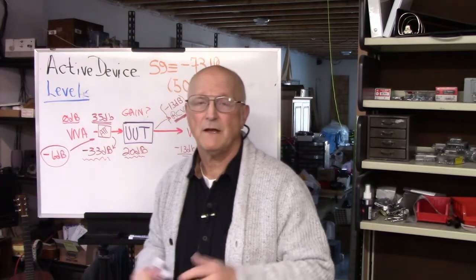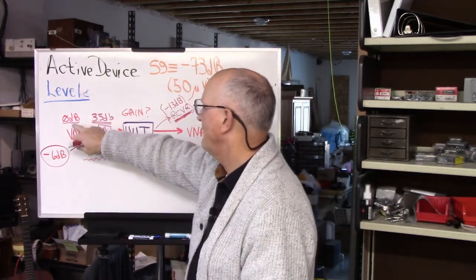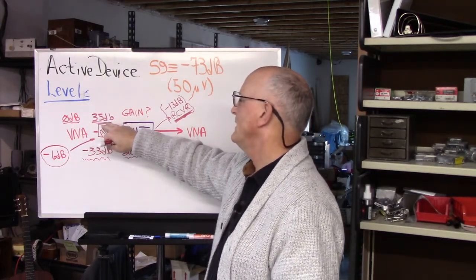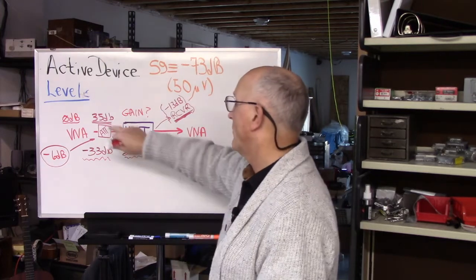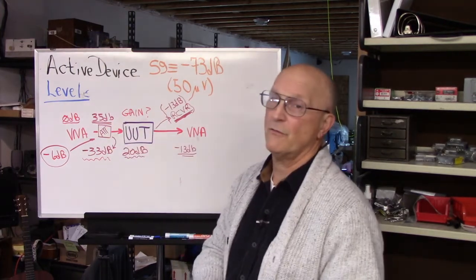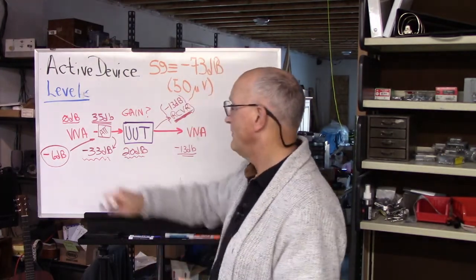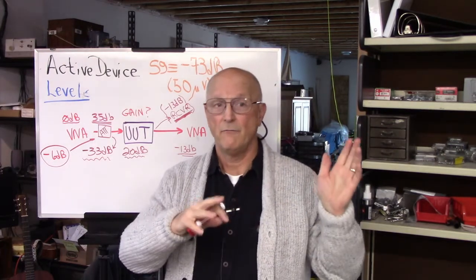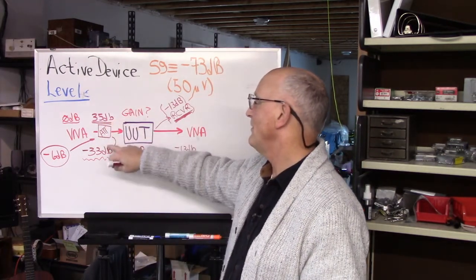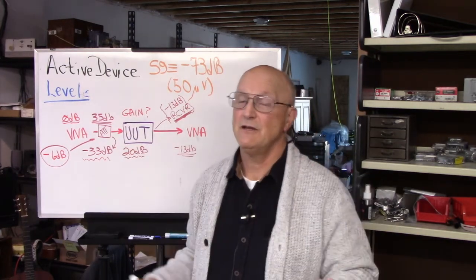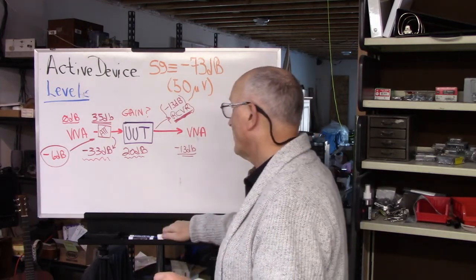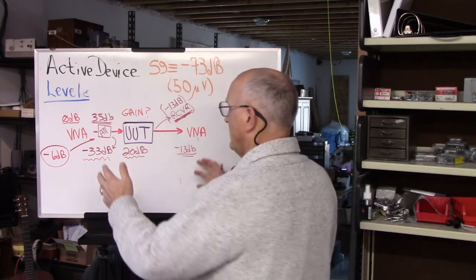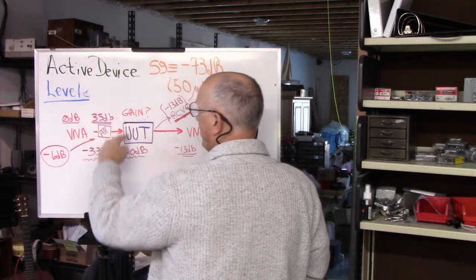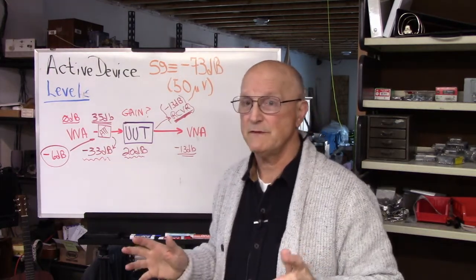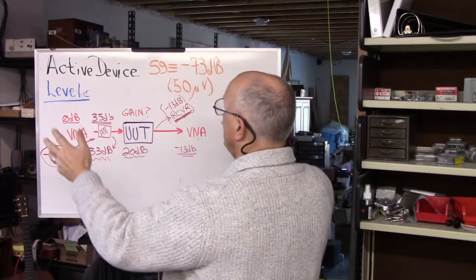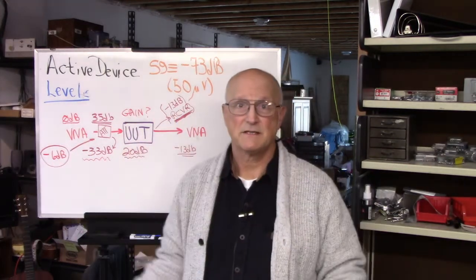Now with my HP VNA, the lowest I can adjust my power level is minus 10 dB, so I could use a 25 dB attenuator here, or a 30, let's say a 30 dB attenuator here with that one. With the Tektronix VNA, the newer one, I can actually adjust the output of my VNA all the way down with a source level of minus 35 dB. So I don't even need to use an attenuator for that one. So what we're going to end up doing is we're going to set up our miniVNA Tiny. We're going to use a step attenuator box to give us about 35 dB of attenuation. And then we're going to calibrate everything and make the measurement. So let's step through that process.